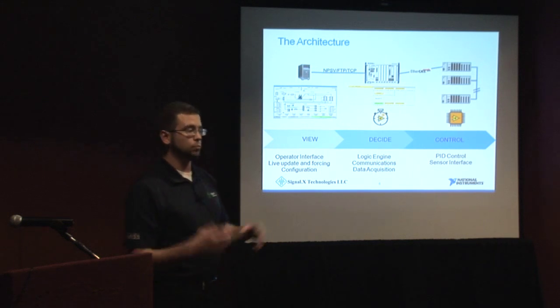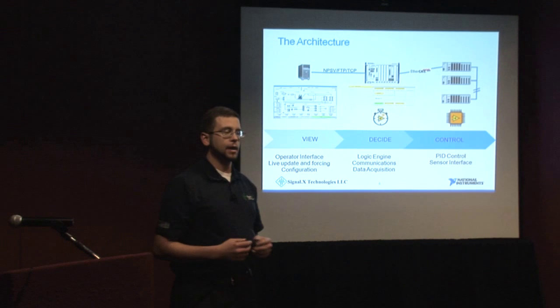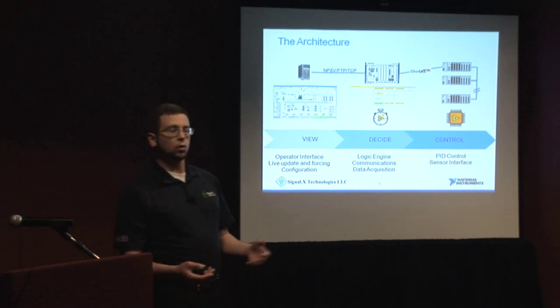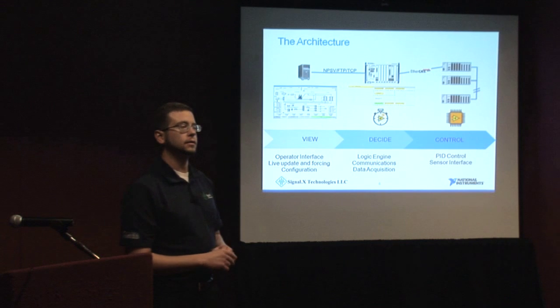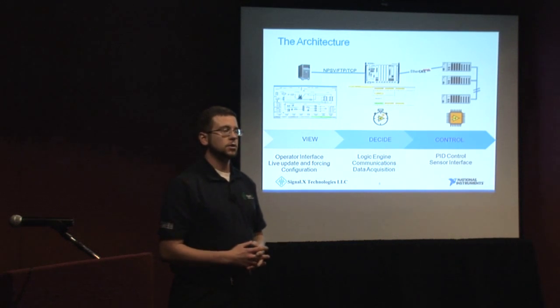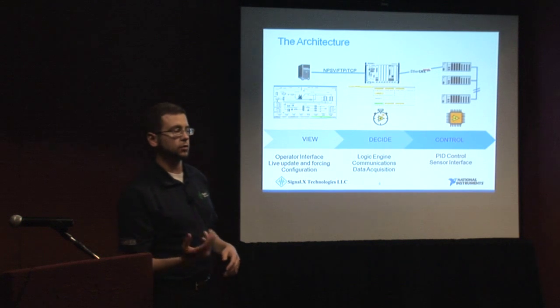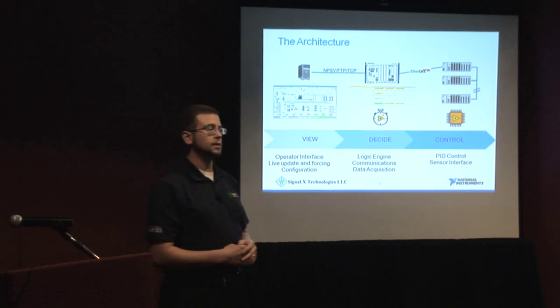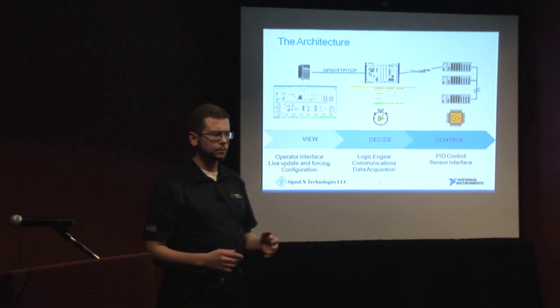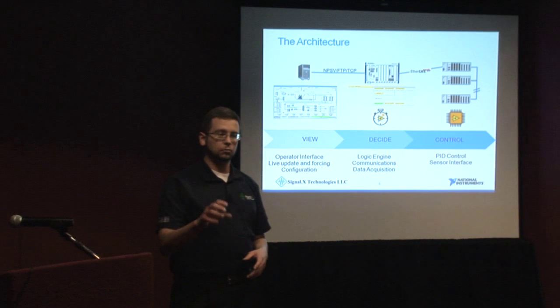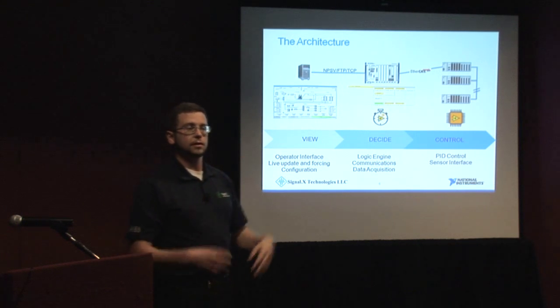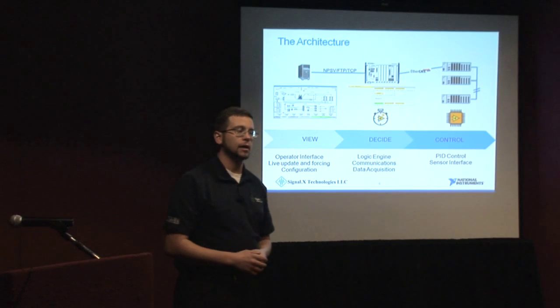The real-time side brings in all of that data and determines what the plant should do — it's responsible for interlocks, safeties, and controlling things like augers and catalytic reactions. It relies on the distributed IO via the EtherCAT chassis to deploy those instructions into real-time control. There are about 10 EtherCAT chassis in this plant, responsible for PID control and connecting to all sensors. All PID control resides onboard the remote distributed IO chassis, so if that link is severed and you have a critical setpoint to maintain, it does maintain it.